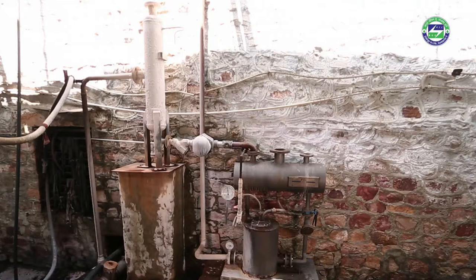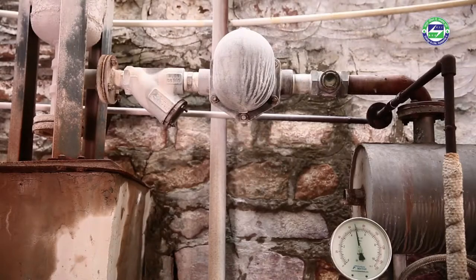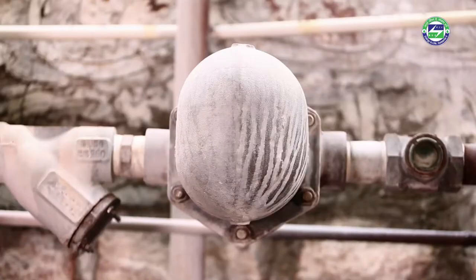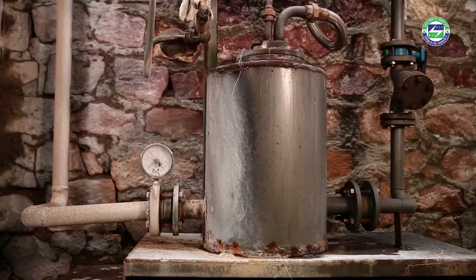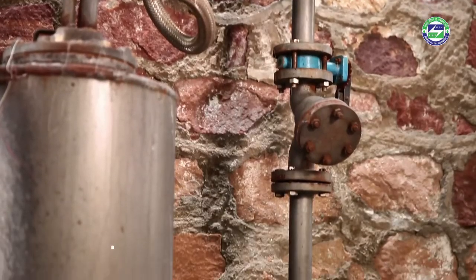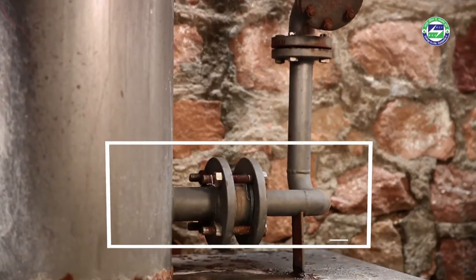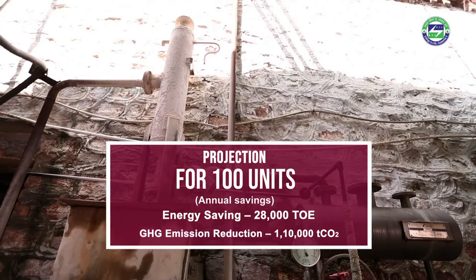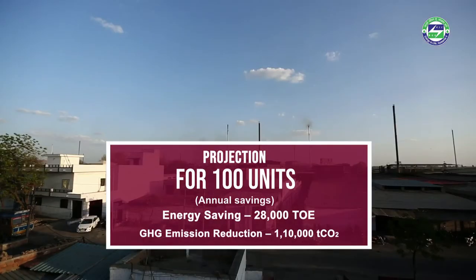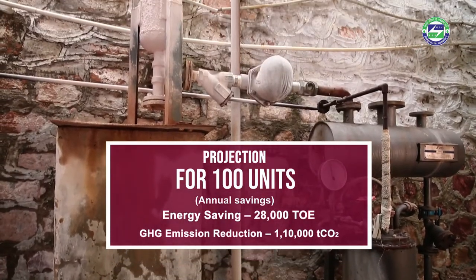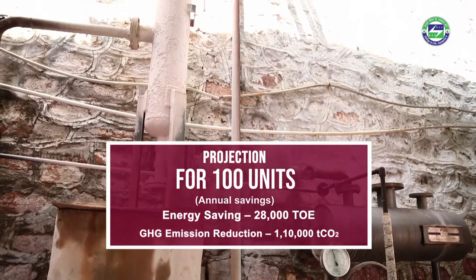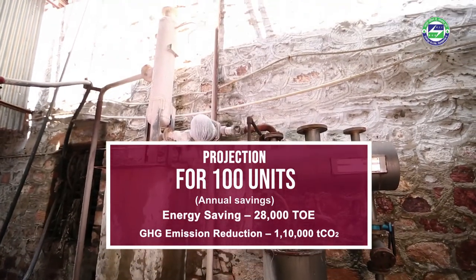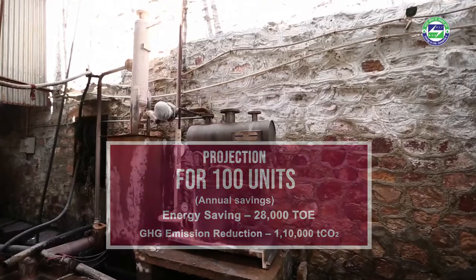The installation requires an investment of rupees fourteen to sixteen lakhs, which can be recovered within one year. The performance of the system depends on the performance of the steam traps, which should be able to trap live steam and separate steam from condensate. The system can be implemented in all process industries using steam for indirect heating. If implemented in one hundred units, this technology can save twenty-eight thousand tons of oil equivalent of energy per annum and one lakh ten thousand tons of CO₂ per annum.